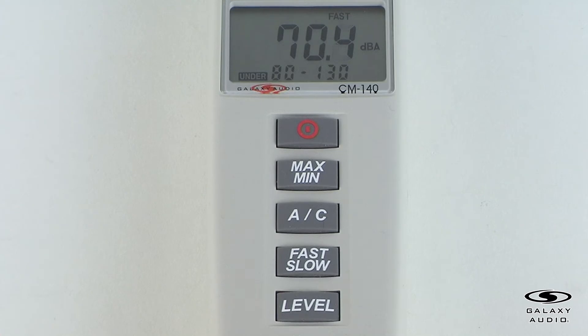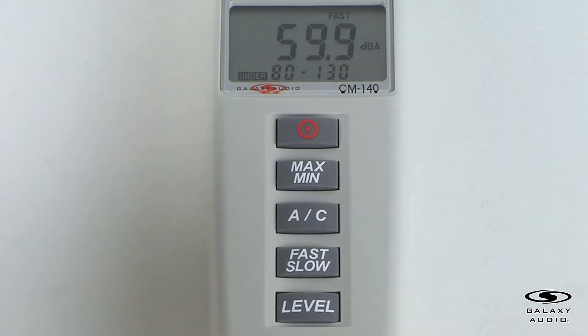To get the most accurate results from the CM140, you must have the level range set at the appropriate level. If the over or under warning indicator illuminates, change the range to where the decibel rating is in the proper level range.